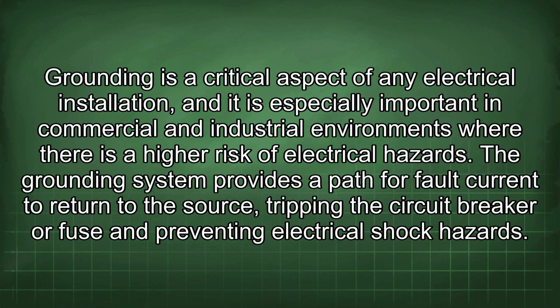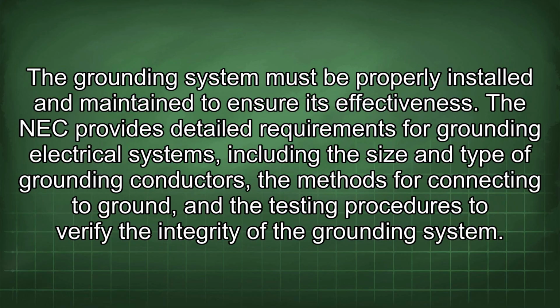Grounding is a critical aspect of any electrical installation, and it is especially important in commercial and industrial environments where there is a higher risk of electrical hazards. The grounding system provides a path for fault current to return to the source, tripping the circuit breaker or fuse and preventing electrical shock hazards. The grounding system must be properly installed and maintained to ensure its effectiveness.